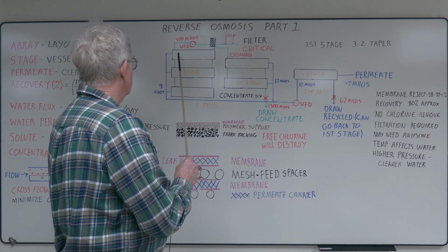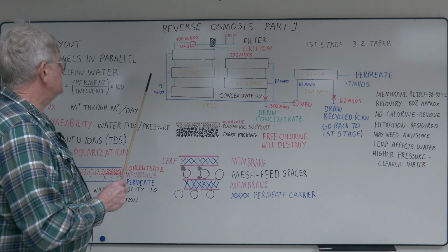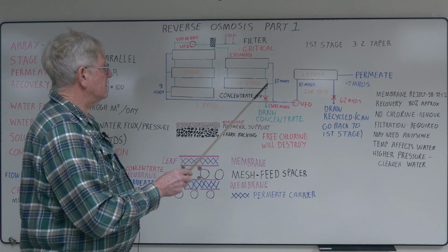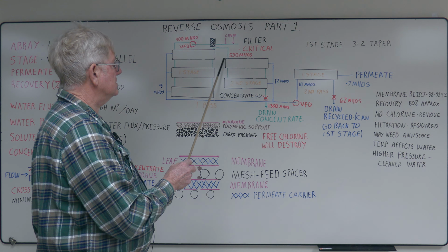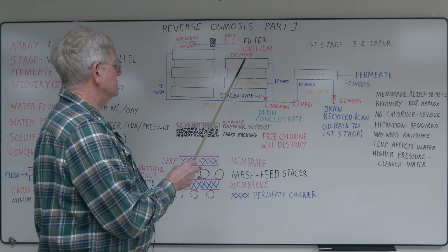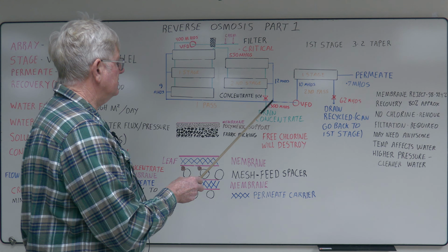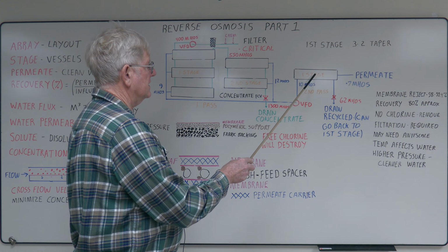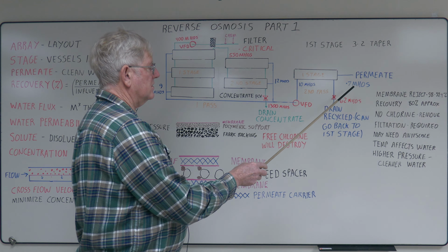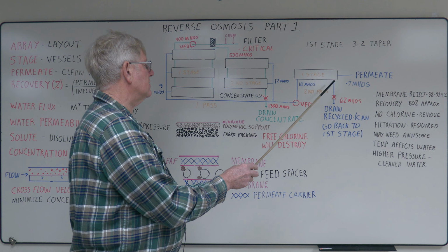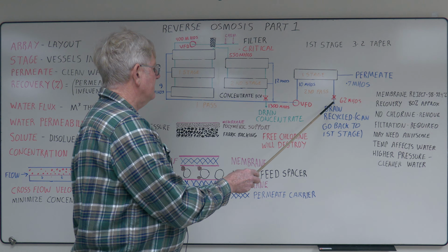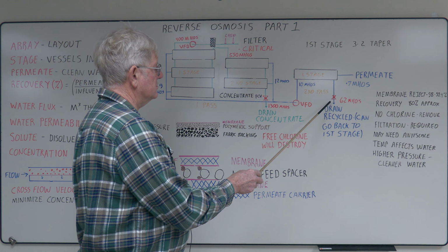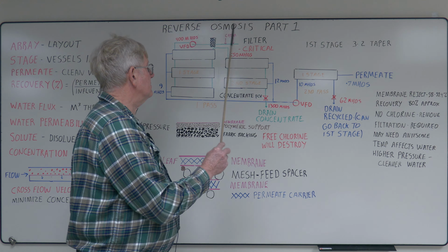Out of the permeate, out of the first stage, it can be 9 micromhos. Now the second stage, it could be 12 because you have higher concentration of minerals in the water. It goes to VFD, you have 10 micromhos feeding the first stage of the second pass. You'll have like 0.7 micromhos permeate, which is fairly clean water. The drain concentrate can be 62 micromhos, which is really very clean water. This can be put back into the suction.